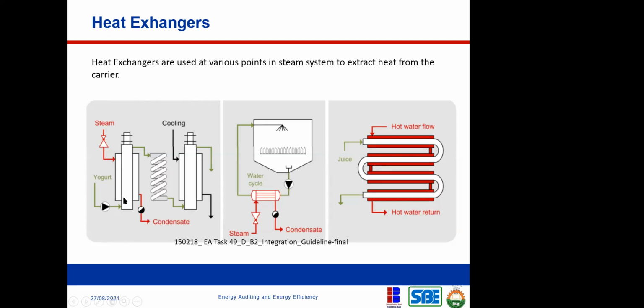So what you have here is a heat exchanger. This heat exchanger will extract the heat and then pass it on to this yogurt. And by that time, the steam will have returned back to condensate. So now the yogurt is coming in here cold, but it's coming out here as hot. Right? So what enables this to happen is the heat exchanger.